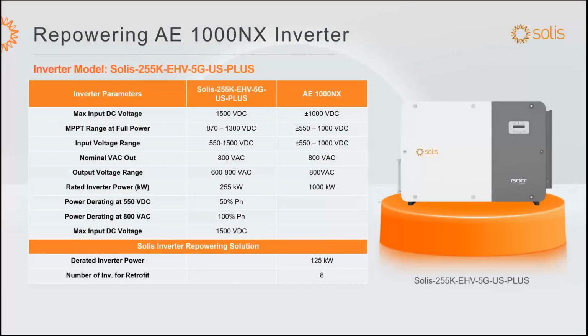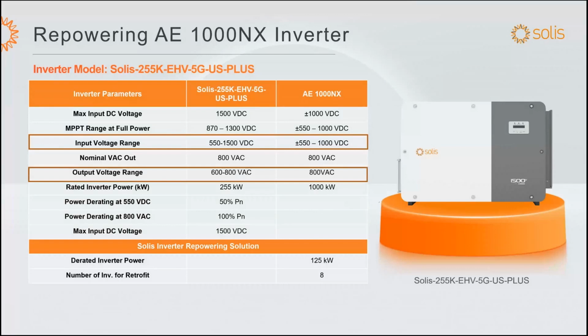The AE 1000 NX is a little bit different inverter, a little bit different model. It has an 800 volt AC output, so that's why we need to use our 255 kilowatt inverter in this case. So this is a higher, bigger power inverter. We check on the input voltage range, and we can cover it with this inverter. And then the output voltage range could be covered as well. So that inverter nicely fits to repower the AE 1000NX, and it will take 8 inverters to repower a 1000NX, and they will be derated to 125 kilowatt, about half the power.